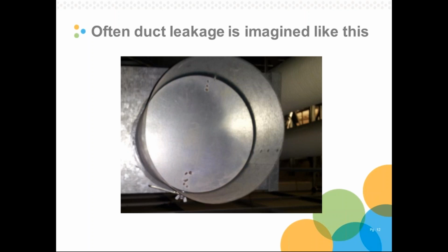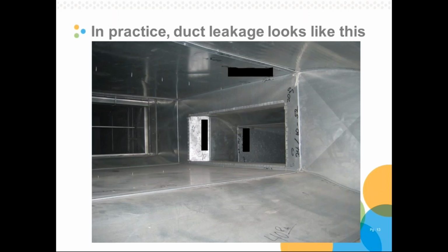This is a branch takeoff that was not completed. Evidently, the contractors decided to supply air through some other branch duct, and their solution here was to cap this branch with a balancing damper. You can see that the balancing damper doesn't do that good of a job sealing the duct, and we get a lot of leakage around the perimeter. That said, although these things do occur, they're not very common. This is generally not what duct leakage looks like in practice. In practice, this is what duct leakage looks like. And I hope to convey here that it's very hard to see.